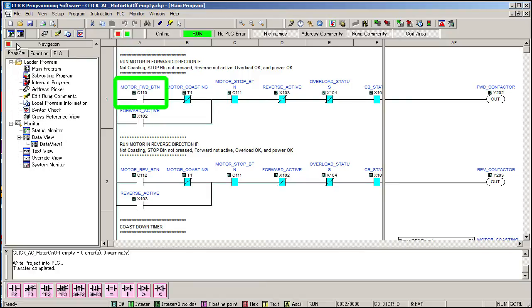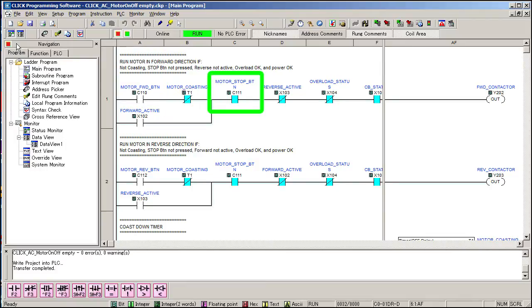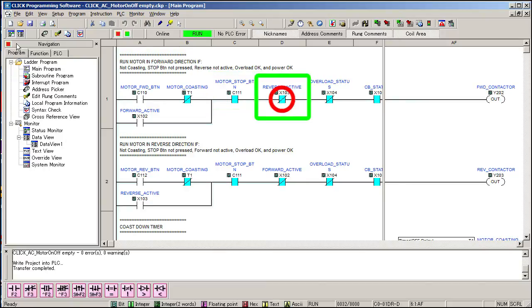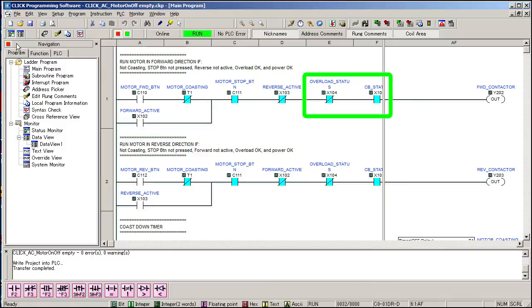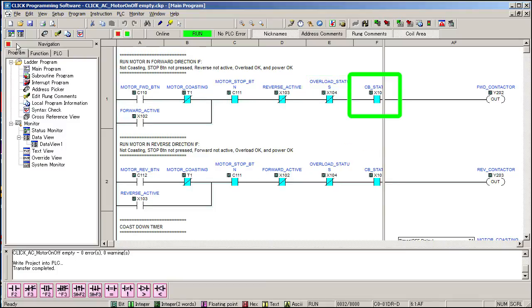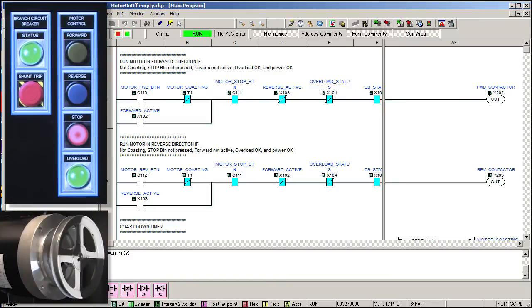So, this tells us that the forward button is not being pressed, the motor is not coasting, the normally closed stop button hasn't broken the circuit, the reverse contact is not active, and the power and the overload are good to go. If we press the overload test button, we see that go inactive and if we flip the motor circuit breaker off, we see its AUX contact open up. Great, looks like things are working.